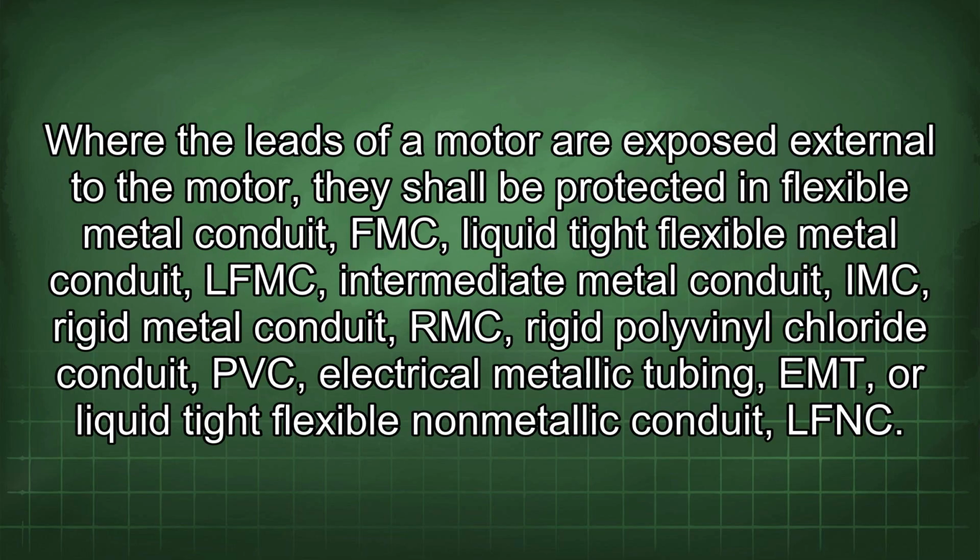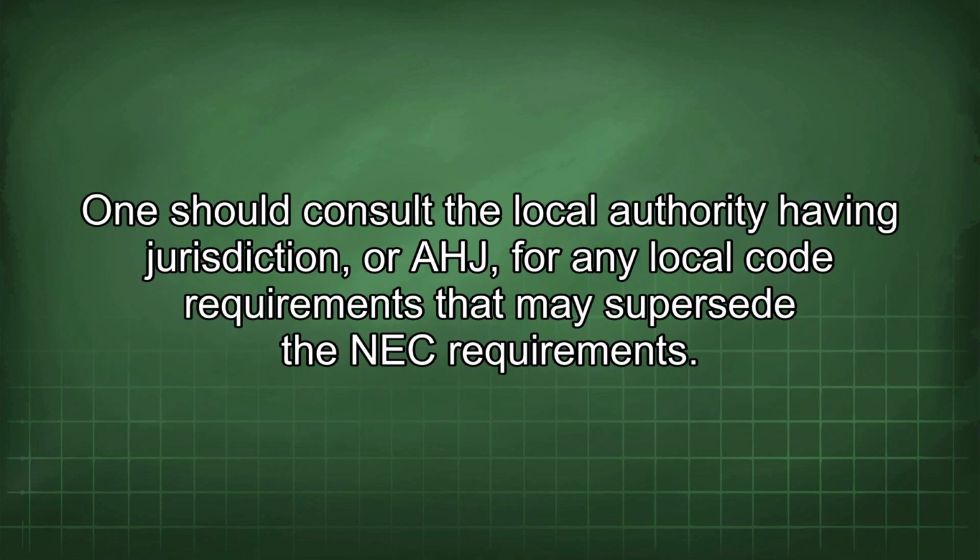Where the leads of a motor are exposed external to the motor, they shall be protected in flexible metal conduit, FMC, liquid tight flexible metal conduit, LFMC, intermediate metal conduit, IMC, rigid metal conduit, RMC, rigid polyvinyl chloride conduit, PVC, electrical metallic tubing, EMT, or liquid tight flexible non-metallic conduit, LFNC. One should consult the local authority having jurisdiction, or AHJ, for any local code requirements that may supersede the NEC requirements.